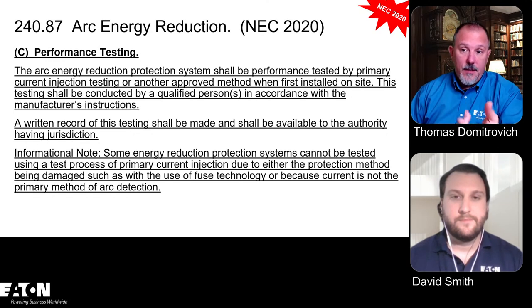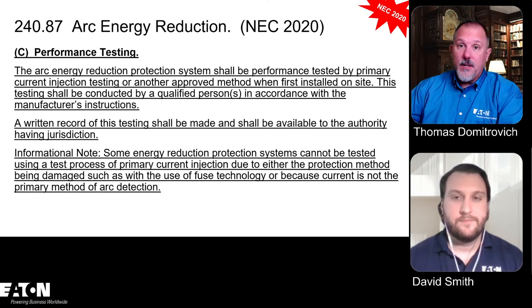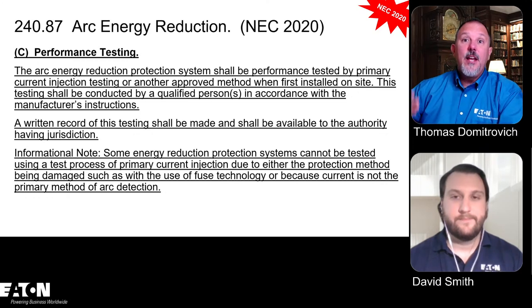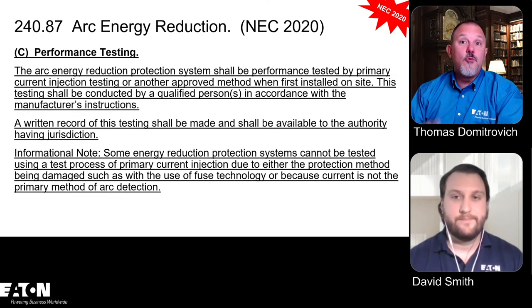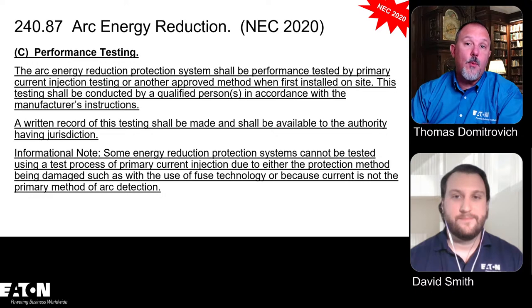With this, and like you said, David, if you're going to do GFPE, I mean, this is 1200 amps, so you're going to have to have ground fault protection of equipment. You're going to have to do your GFPE testing, and that requires primary current injection testing. So you can kill two birds with one stone. Don't hire the guy to do GFPE and then go, oh crap, I need you to go back out and do 240.87. It's going to be more expensive, two trips, hauling equipment out twice. Get it all done at one time.